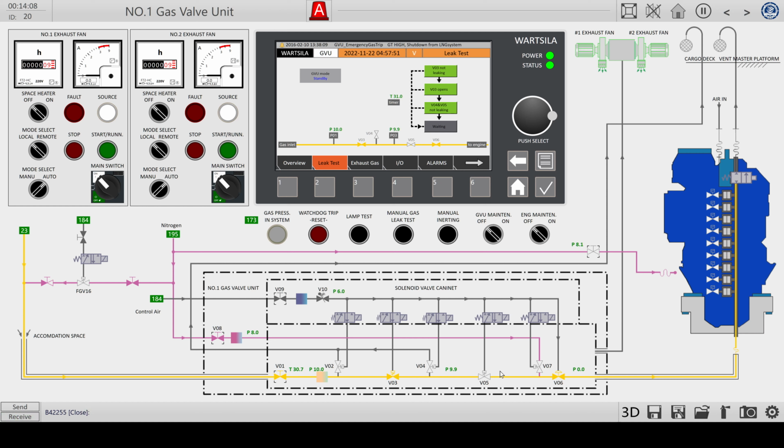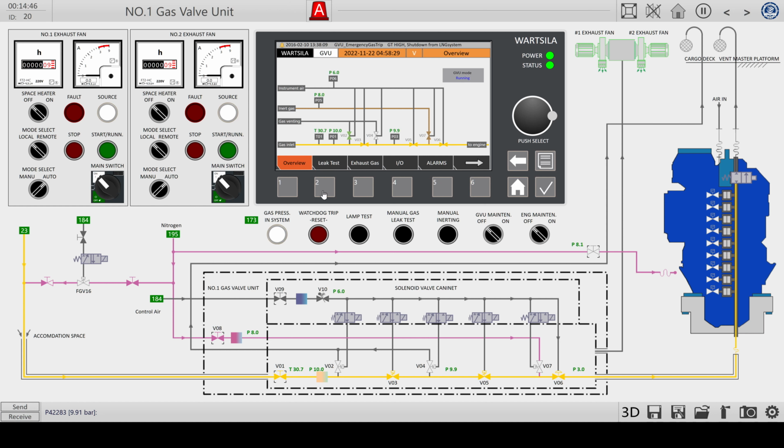You see there is pressure over here. And as there is no pressure over there, that must mean valve 5 is okay. It's also the green light, so it knows it's going to 50 seconds, so 10 seconds to go, and then this automatic test is done. Yep, test is done. You see now the unit is in running mode.